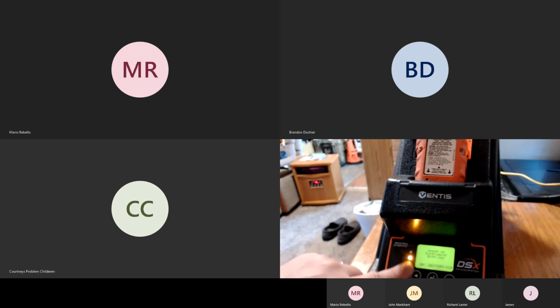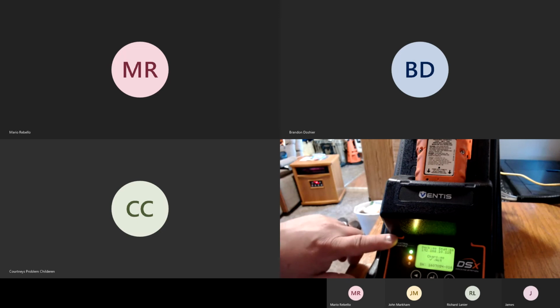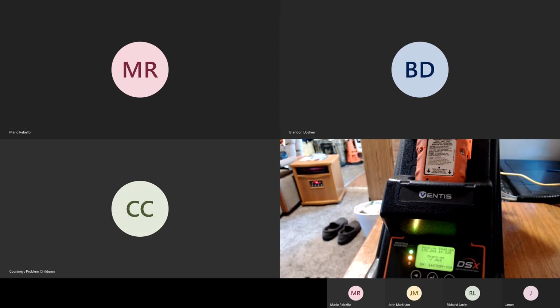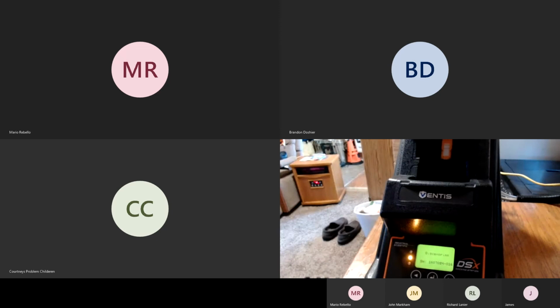Now, right here, it's going through, and it says reading settings, updating instrument settings, and it's doing all that maintenance for me. I don't have to do anything, because it's following along with what I told it to do inside of my software. Now, it's going through downloading alarm events, downloading data log, and now it's done. You'll notice I have a green and yellow light. Green and yellow says, hey, I'm done doing what I need to do, and I'm just charging, because the docking station will act as a charger as well. Whenever it's fully charged, the yellow light will go off, and the green light will stay on. At this point, you can take the instrument out, and we can go ahead and use it.